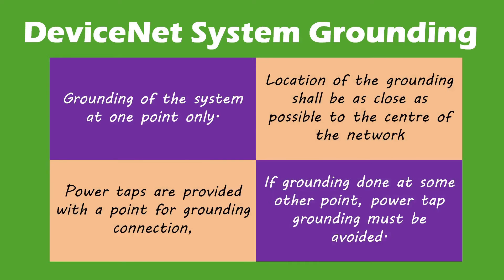In a DeviceNet network, grounding of the system must be done at one point only. The location of grounding should be as close to the physical center of the network as possible. The grounding connection should be made at a power tap that has a terminal for grounding. If the network is connected to ground at some other point, ground shall not be provided at the power tap. It must be ensured that only a single ground connection exists in the network.